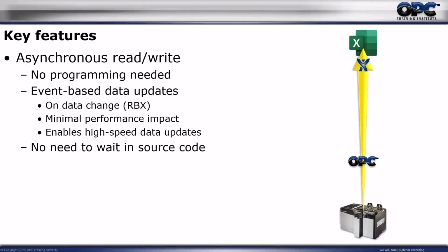As far as reading and writing, all of this is done asynchronously, which means you get report by exception or on data change, subscription. In other words, you don't have to go to the OPC server and keep saying, what's the value? What's the value? What's the value? There's no need to do that whatsoever. OPC Expert does that for you, brings the value right into Excel. So it is event-based.